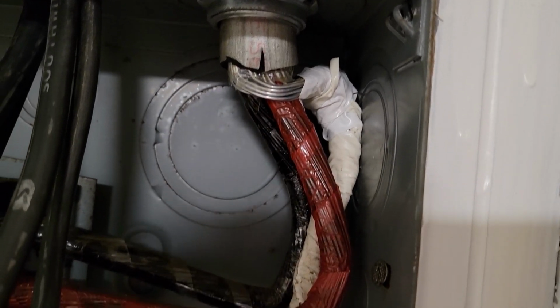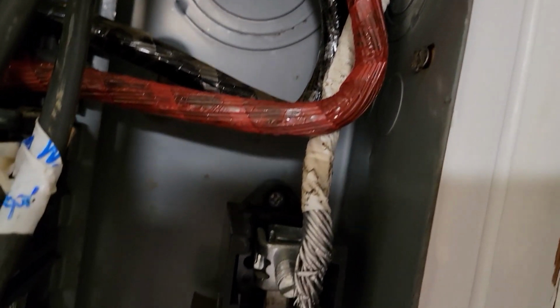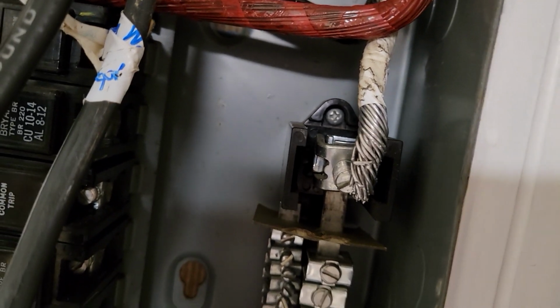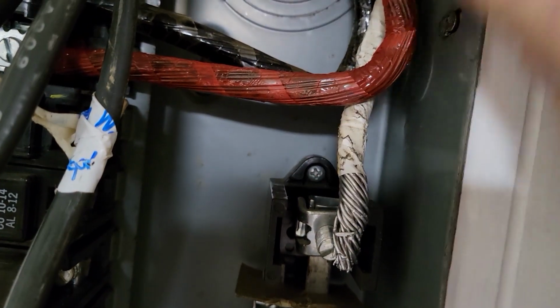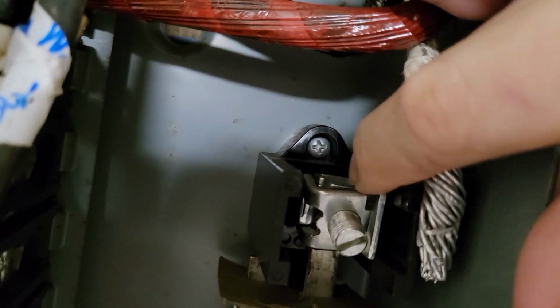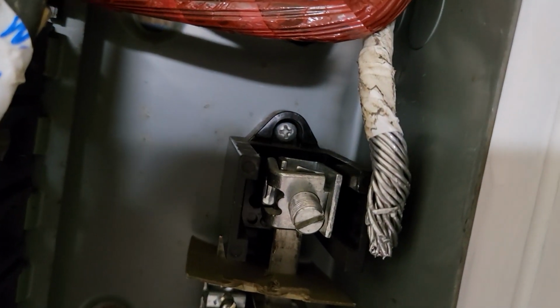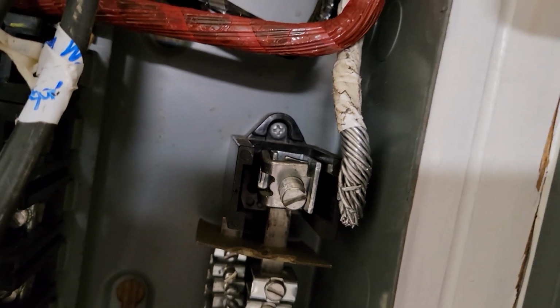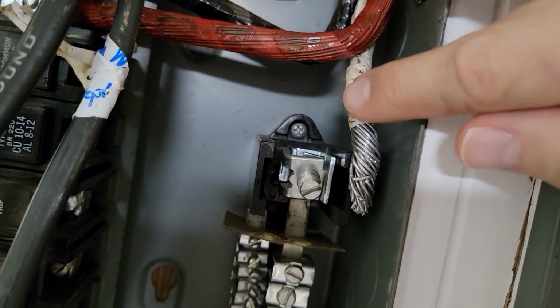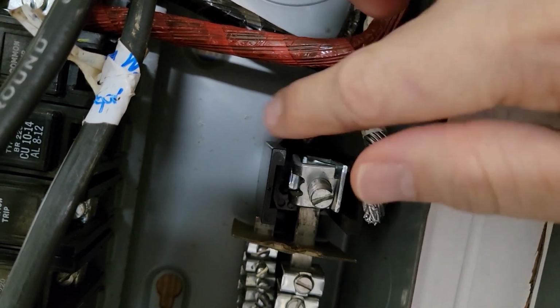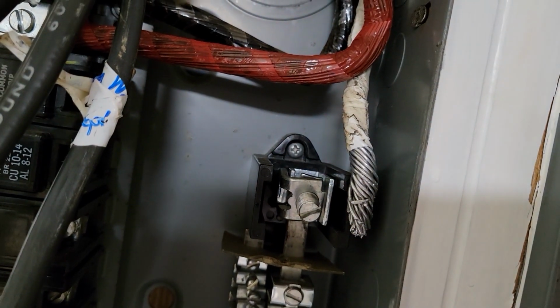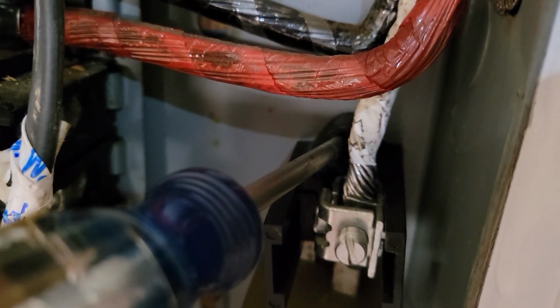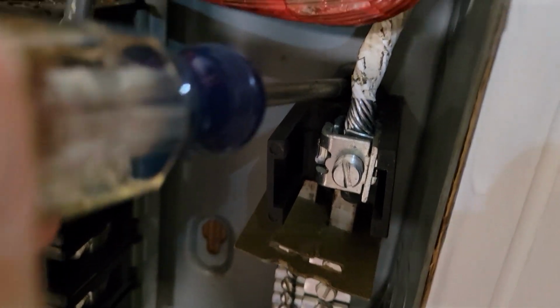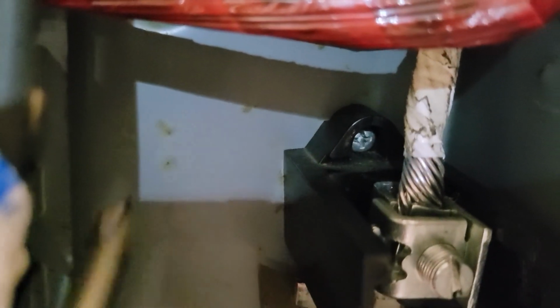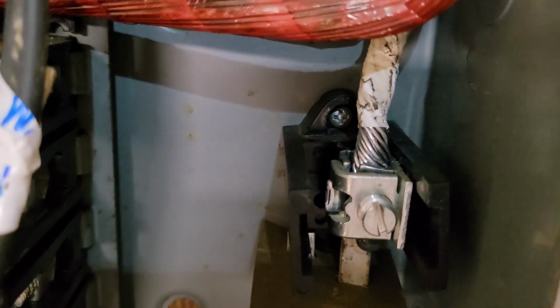I've managed to get the neutral cable behind the red coming down, but I really have no ability to move that cable up so I can get to the clamp. So I'm going to try plan B, which is to remove the neutral bar, attach this to the neutral bar, then attach the neutral bar to the box. I added the antioxidant compound, attached it to the neutral bar, and had enough room to tighten that screw back there that mounts the neutral bar to the box.